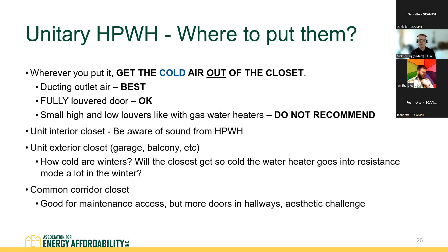If you have it in a common corridor closet, this is an interesting approach we're starting to see on some projects, a number in Southern California, where they put units in closets adjacent to the apartment but open to a common corridor. That way maintenance can access them from the corridor, but they're plumbed into the apartment. This means more doors in the hallway, which could be an aesthetic challenge. As the owner, that may or may not matter, but we're seeing more owners and developers take this approach for individual heat pump water heaters.